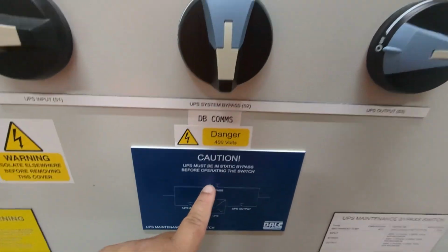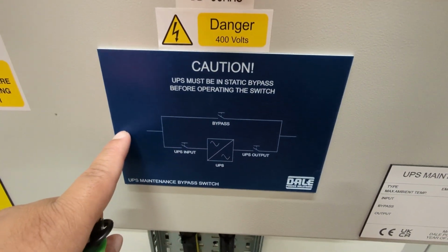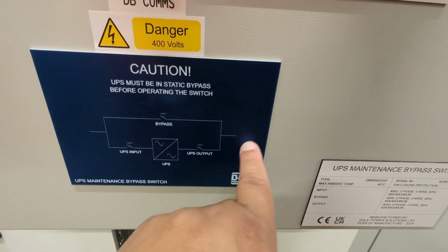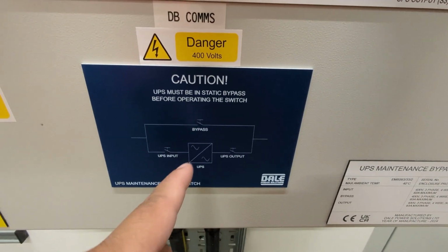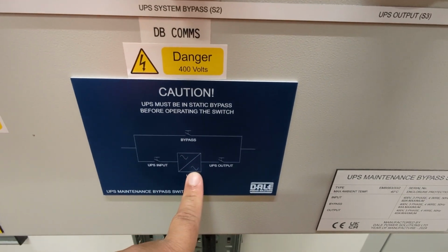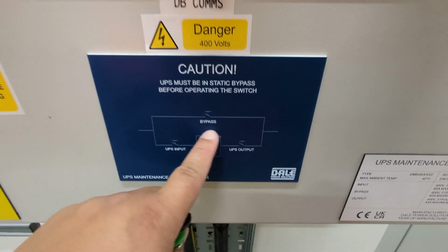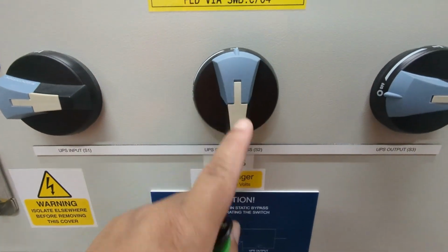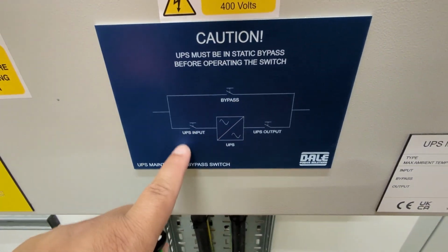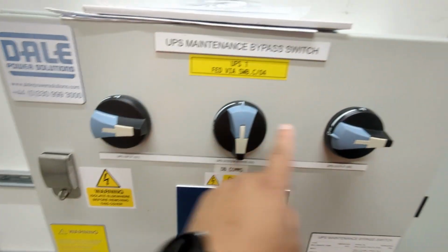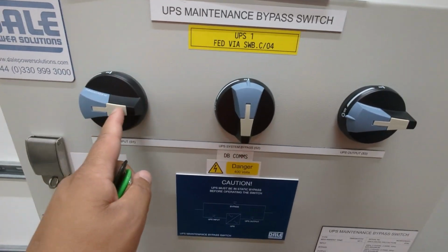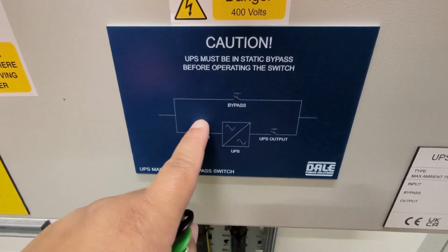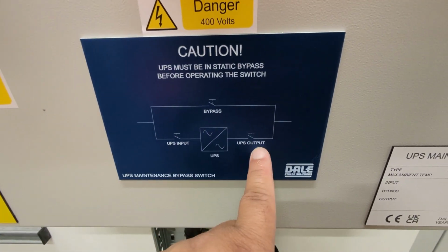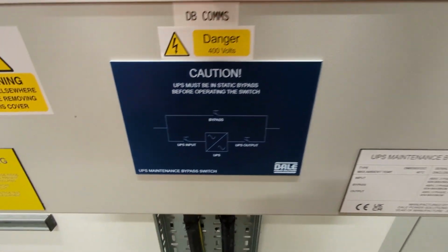This UPS bypass switch is on, so the incoming feed just goes straight through to the output. If we want to turn the UPS on and use it, we close this switch, open this switch to turn it off, and bring in these two contactors or isolators. Close those, and now the building feeds the UPS and the UPS feeds the output. So if you lose the building supply, the UPS will keep feeding.